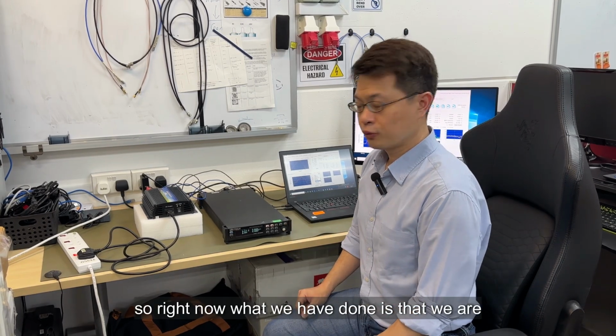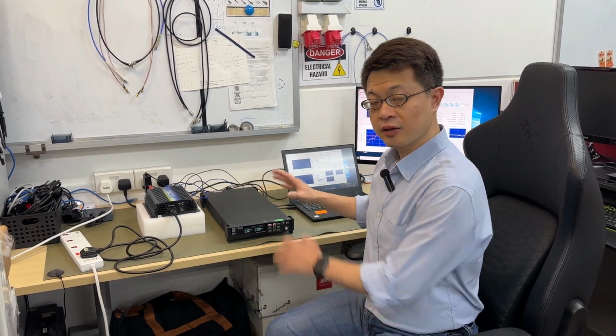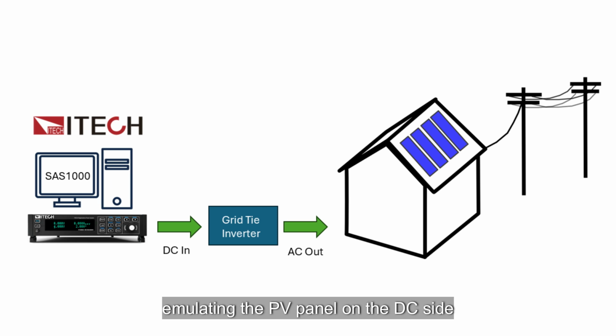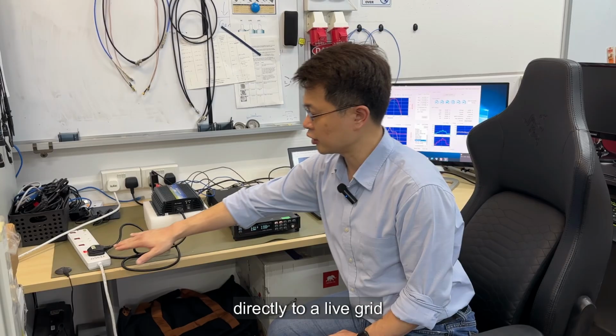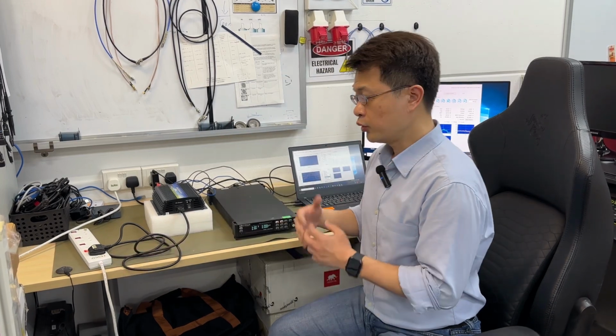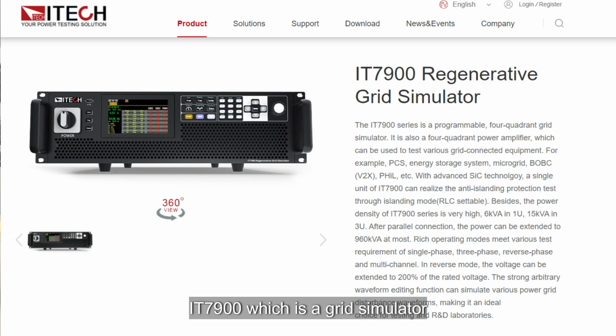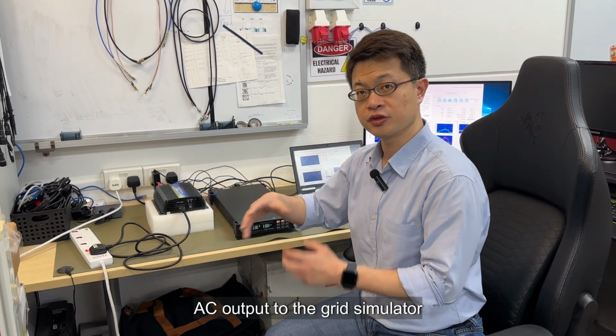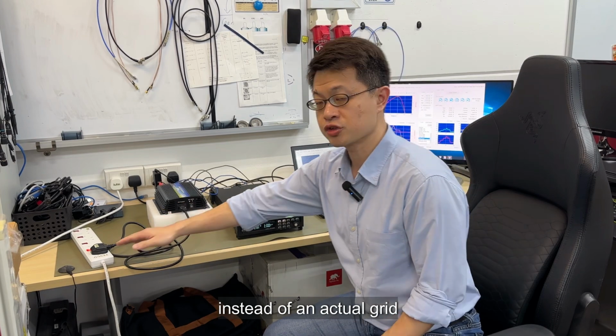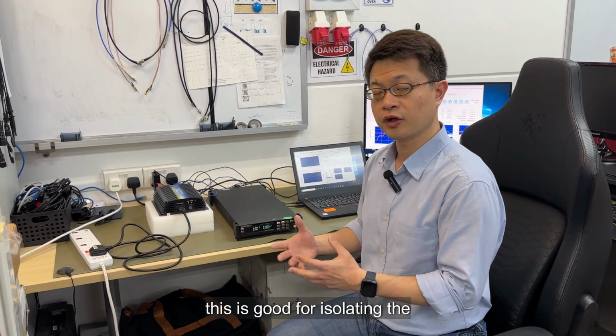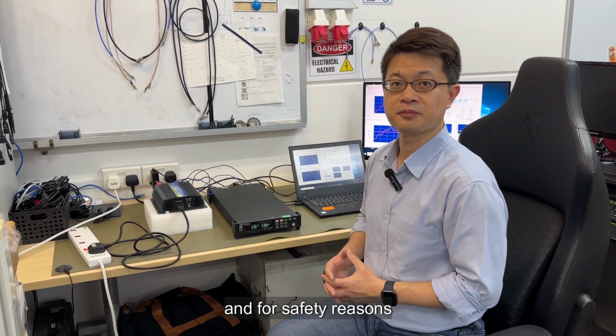So right now, what we have done is that we are emulating the PV panel on the DC side, and the grid tie inverter is connected directly to a live grid. We also have the IT7900, which is a grid simulator, and you can connect the AC output to the grid simulator instead of an actual grid. This is good for isolating the test and for safety reasons.